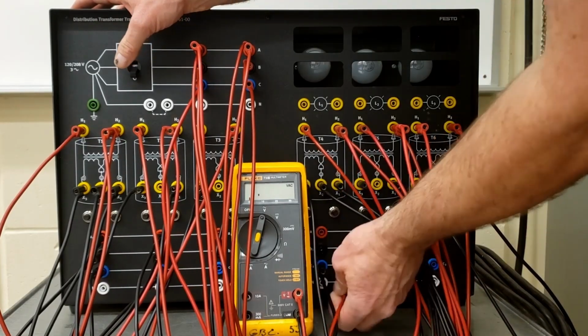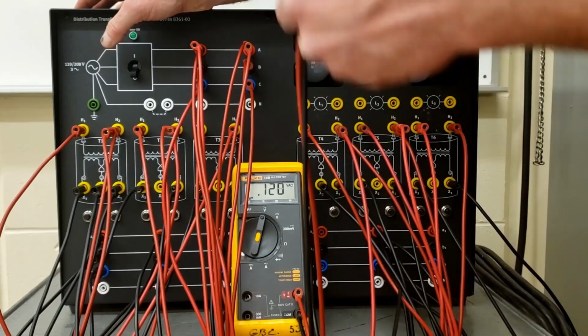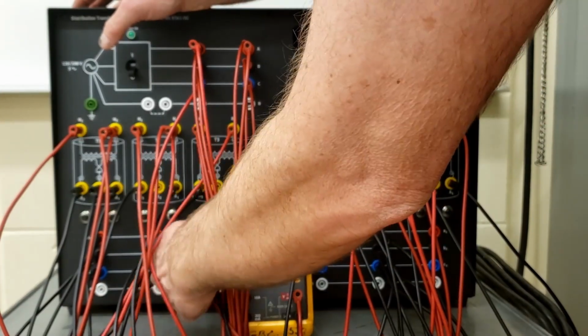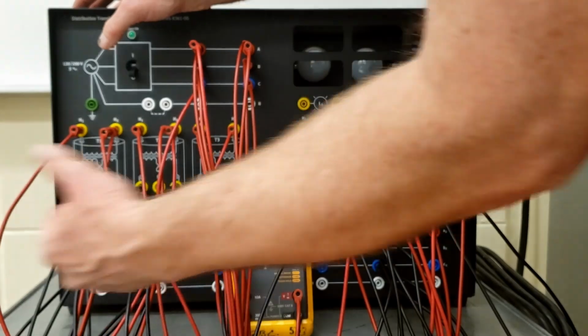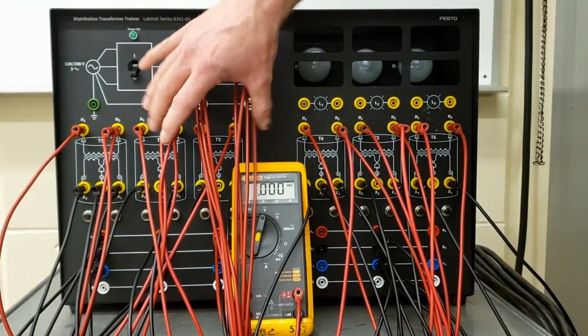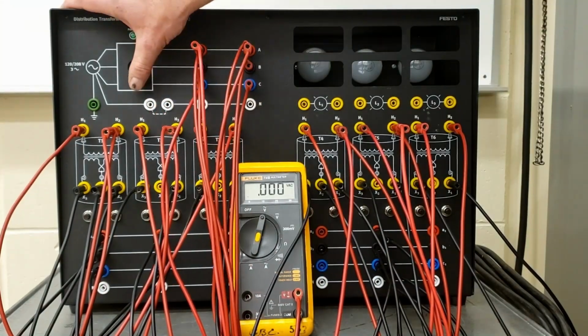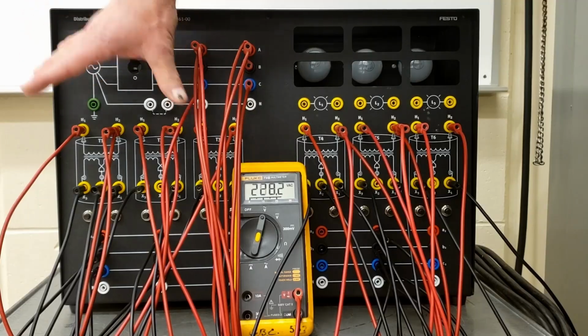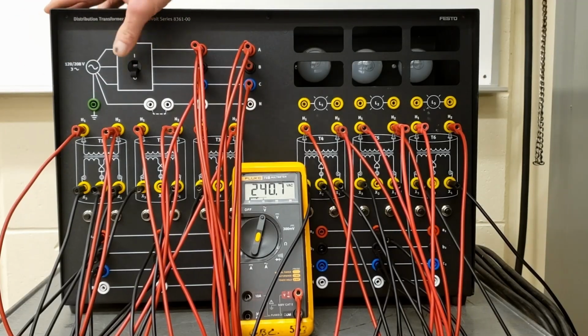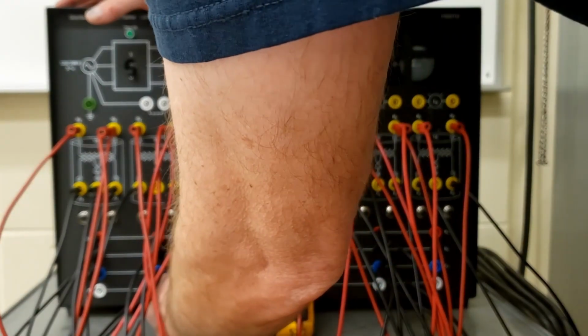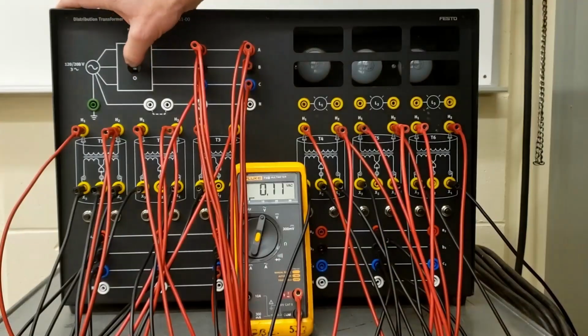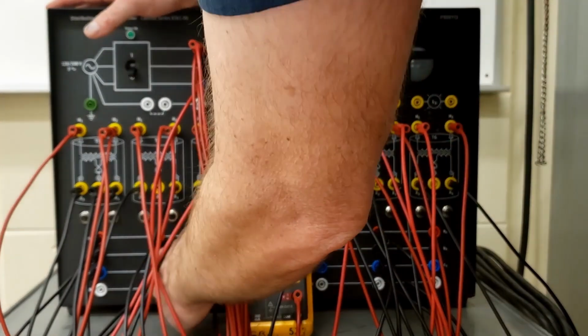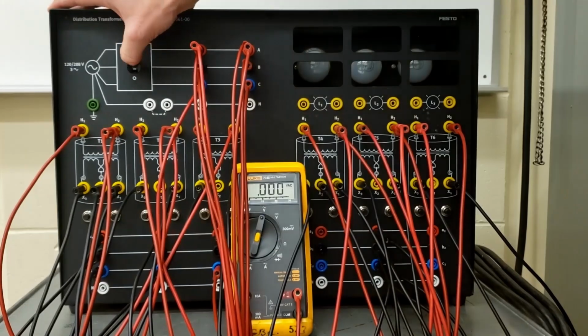Just double checking on the other transformer here. It's messy, eh? We may not be able to use those shrouded leads because look at how many leads you actually need just to get this one configuration done. This is A and B on the first bank of transformers, so 240 there. B to C should be 240, and then C back to A should be 240 as well.